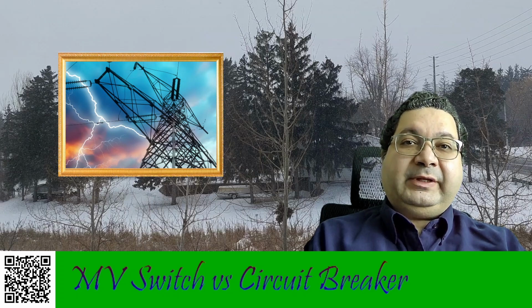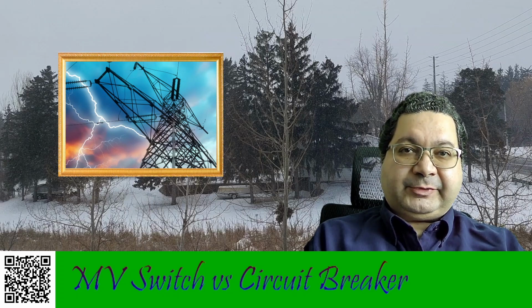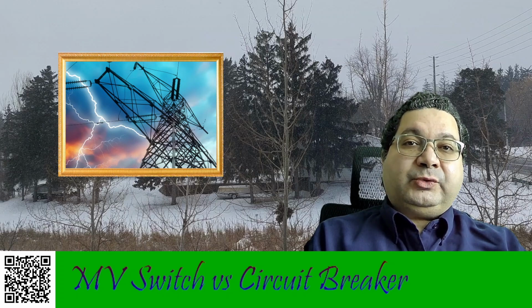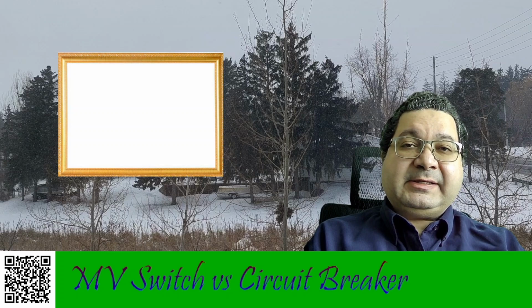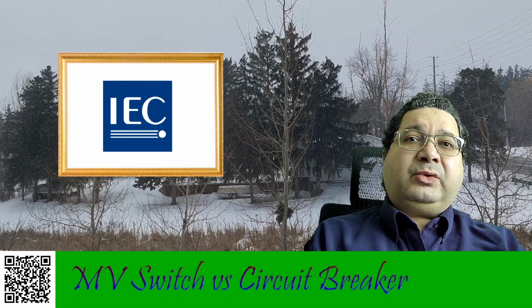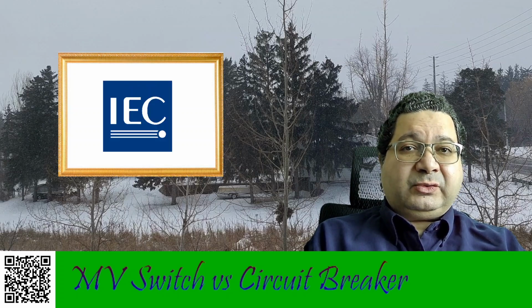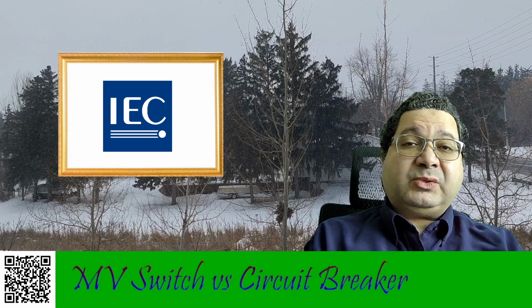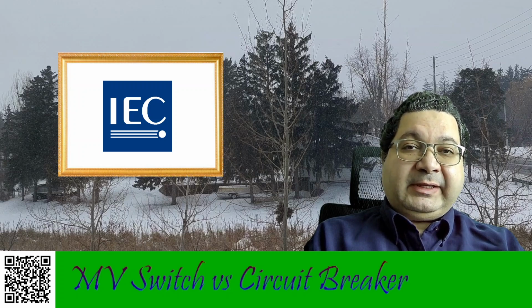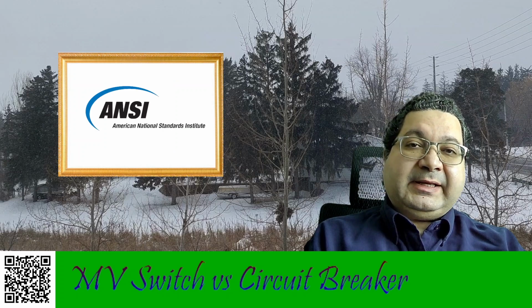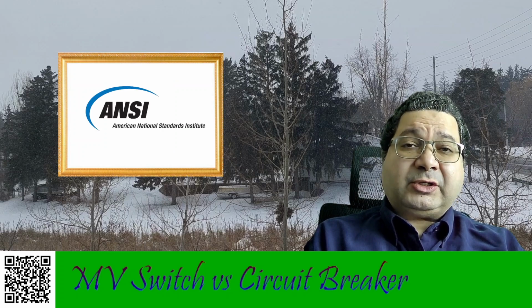What is the difference between a medium voltage switch and a medium voltage circuit breaker? A medium voltage switch is known in Europe and IEC as a disconnect switch, or a disconnect only. So in Europe, a disconnect switch is basically a switch that provides isolation as well as the capability of making and breaking a load.